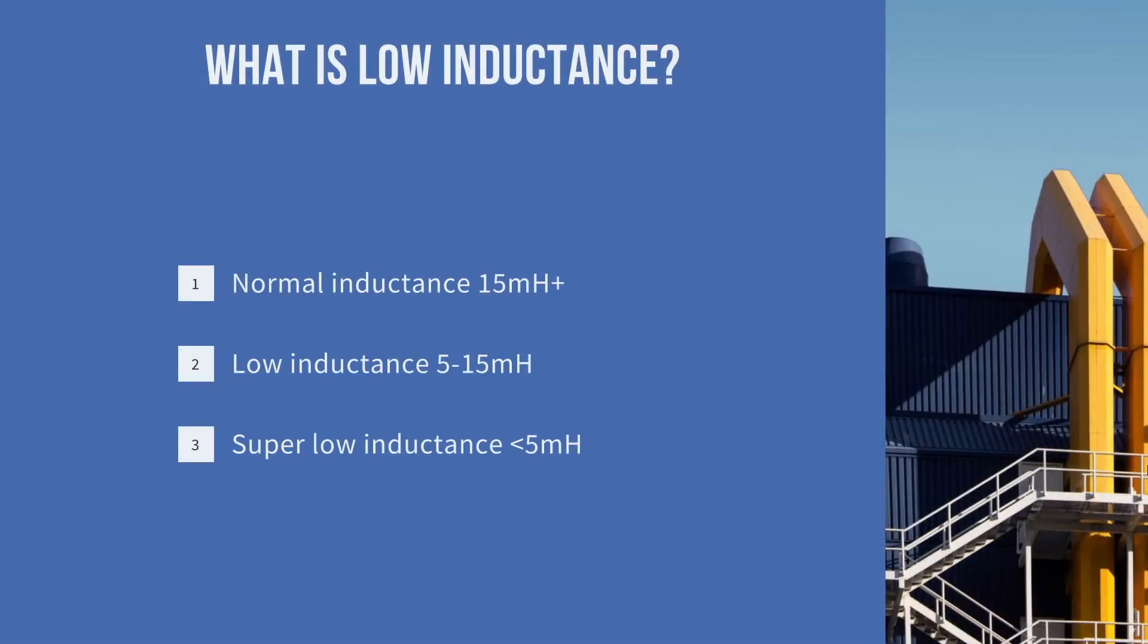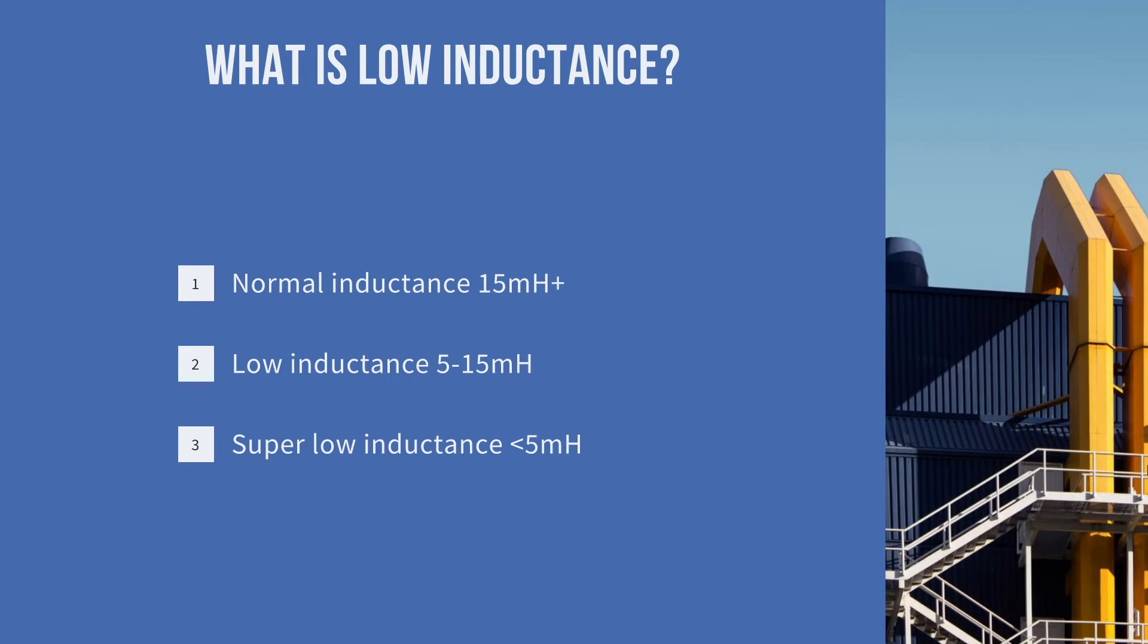What do we mean by low inductance? This isn't an industry recognized definition, but the way we define them is normal inductance 15 microhenry or above, low inductance 5 to 15 microhenry, and then super low inductance which is anything less than that.